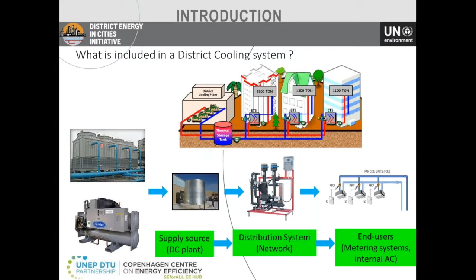So what does the district cooling system change compared to a standalone system? Actually, the district cooling system just replaces the cooling source, including chillers, cooling towers, and circulating pumps inside the building, with a heat exchanger. Everything else inside the building, like HVAC equipment including air handling units or fan coils, stays the same. This figure shows that when you replace the cooling source inside a standalone building, you can have a rooftop garden instead of cooling towers.